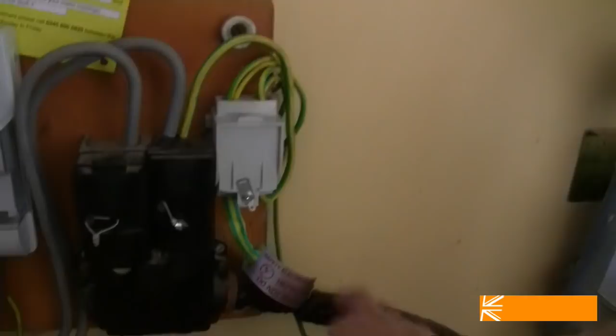Anyway, the other Western Power engineers have decided not to do anything with it other than tidy up the sheath of the cable, and effectively PME'd it because they've tied this earth block to the neutral here. So that's their way of fixing the fault - they know the earthing on the sheath of the incoming is bad from the street, so they've tied it to the neutral at the head here. So when we do our test later on, we ought to get the number down.